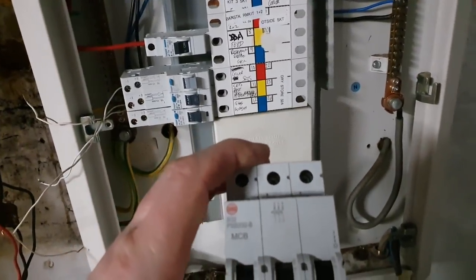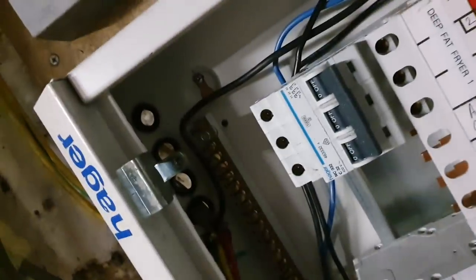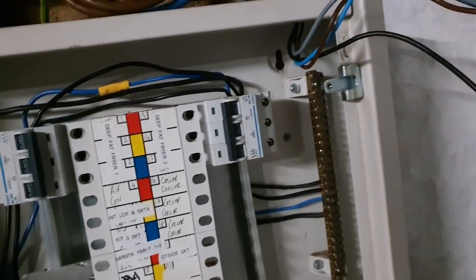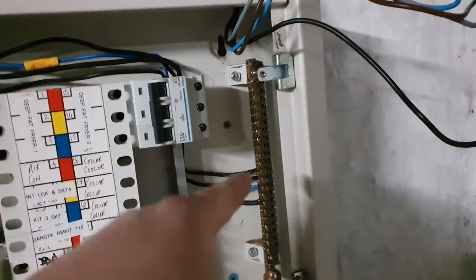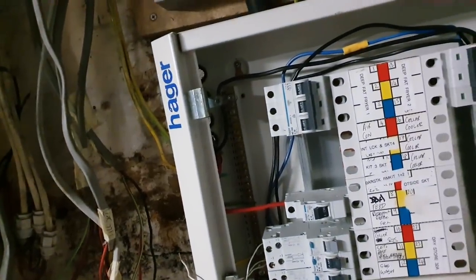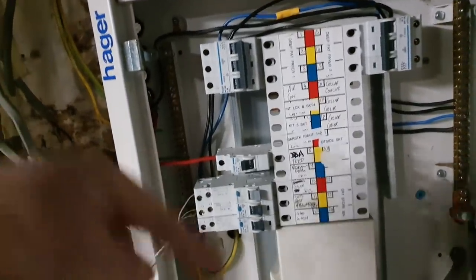I'm waiting for another one to come in because this is a Wylex MCB and I'd like to have Hager in there. I've also put rubber grommets in all of the cutouts they've made because there weren't any before. We are also rerunning the terminations, making sure the routing is proper — that whatever's on circuit 10 corresponds to the neutral wire going into number 10 and the earth wire going into number 10 as well. We're doing full impedance testing on all the circuits, insulation resistance testing, everything I know how to do.